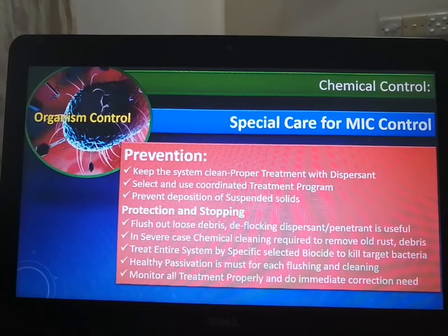A coordinated treatment program means a good quality corrosion inhibitor, a synergistic scale inhibitor, and a biodispersant, all coordinated and integrated with the microbiological treatment program like oxidizing biocide, non-oxidizing biocide, or a multiple product. The treatment must have a coordinated approach, with full focus on corrosion, scaling, biofouling, microorganism fouling, oxidizing and non-oxidizing treatment.